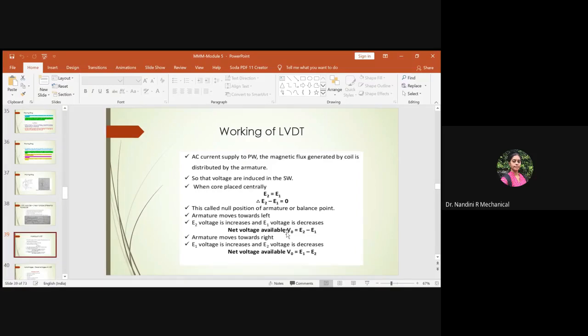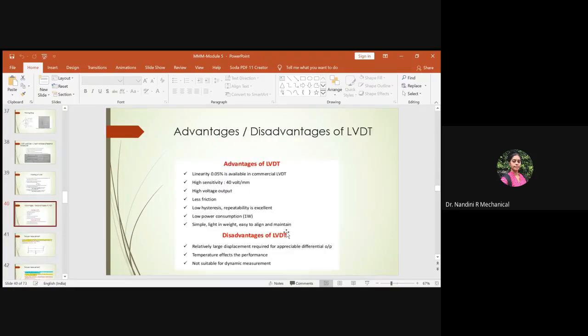After knowing the working of LVDT, you should also understand its advantages and disadvantages. The first advantage is it is able to achieve linear displacement measurement right from 0.05 percentage, available in commercial LVDT. So with commercial LVDT, this instrument is even able to sense and measure the linearity deflection at 0.05%.